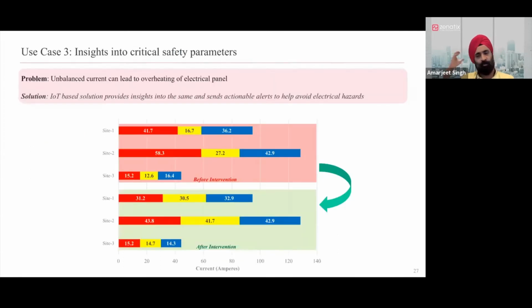For a three-phase system, you should try to keep balanced load across all the phases. On top is how the different currents were before an intervention happened, and when our systems detect this current imbalance, we raise alerts to the customer, who takes proactive action, and only when the current is reasonably balanced across the three phases does that alert get closed. Many of these things would go unnoticed unless you're looking at specific insights from the data, and even a prerequisite to that is exposing the data to a system running several of these analytics.